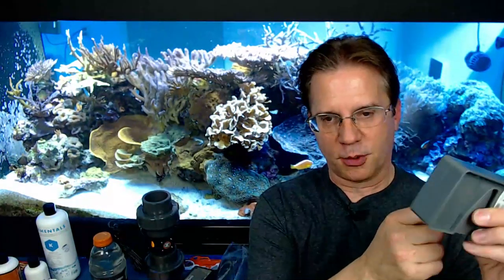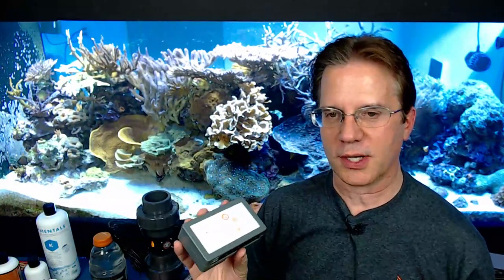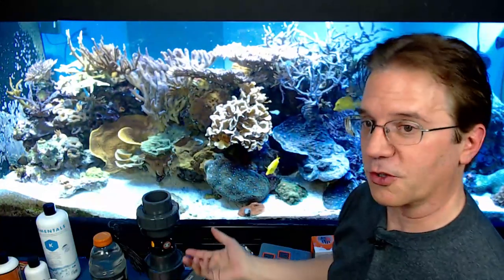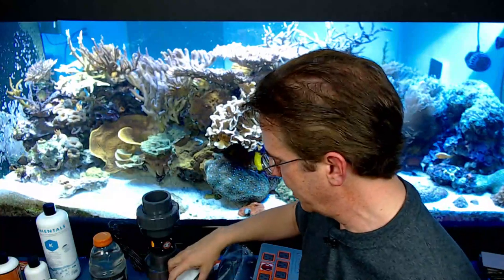The beauty of Aquabus cables is you can run a cable from device to device to device, daisy-chaining everything. As long as everything is connected all the way down, even the device at the far end will reach all the way back to the brain at the first end. So if you're running out of ports, find something with more ports to add—maybe the PM1 has extra ports you could use, or add another Energy Bar, since there's always more things to plug in. That gives you 3 to 6 new Aquabus ports to use.